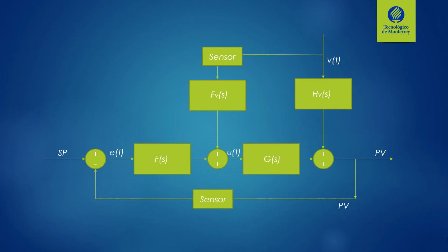The feed-forward controller is appropriate for those cases in which it is desired to have better rejection of the disturbance and that we do not have a secondary variable of the process that is measurable, which responds earlier to the manipulations in the final control element and provides information about the interruption that the system will have. It also applies to those cases in which there are interruptions in the system that cause increased costs, and that this interruption is due to a specific disturbance.